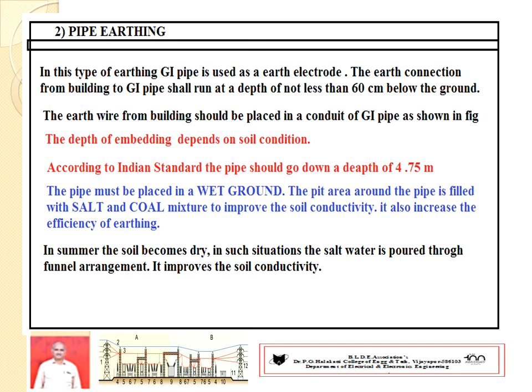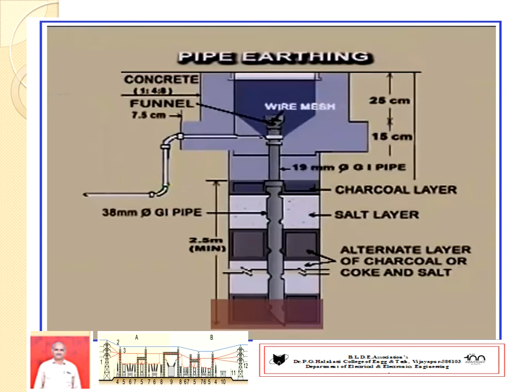The pipe must be placed in a wet part of the ground. The pit area around the pipe is filled with a salt and coal mixture, which improves the soil conductivity, or you can remember it reduces the soil resistivity. So, it increases the efficiency of earthing. In summer days, the soil becomes dry. In such situations, salt water may be poured through the funnel arrangement, which increases the soil conductivity. You can see the diagram of pipe earthing.